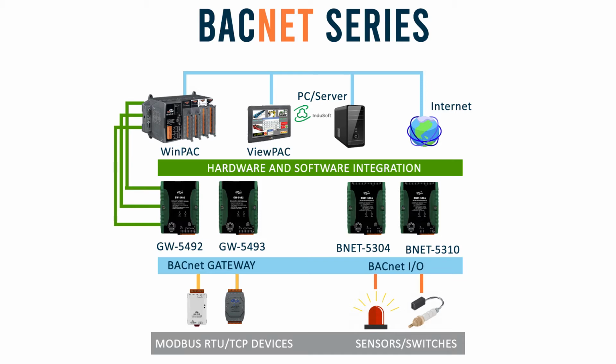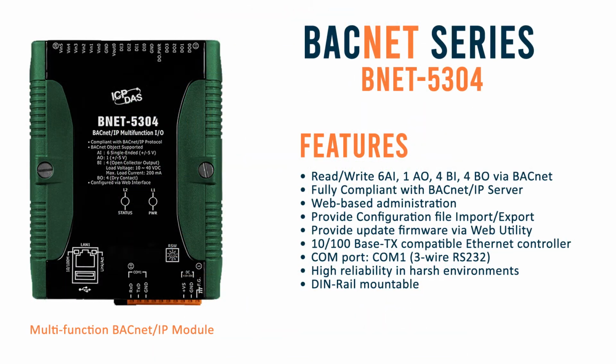perform. The BACnet protocol defines a number of services that are used to communicate between building devices. It also defines the number of objects that are acted upon by the services. The objects include analog input, output, and value, binary input, output, and value, multi-state input and output, etc.